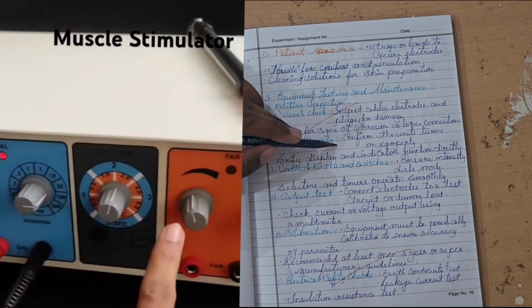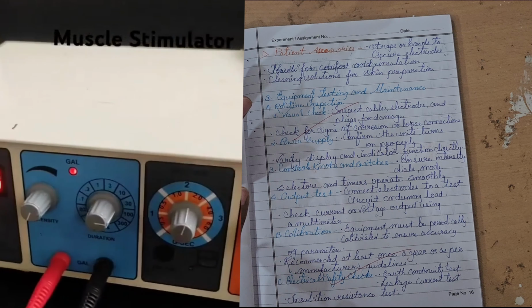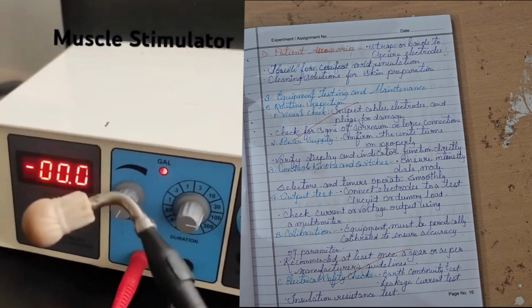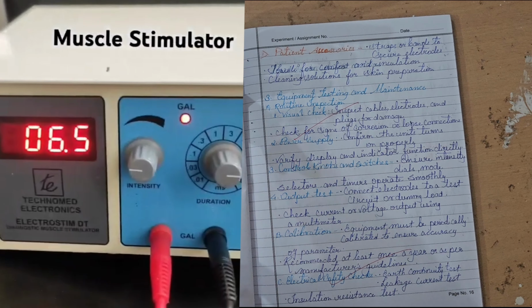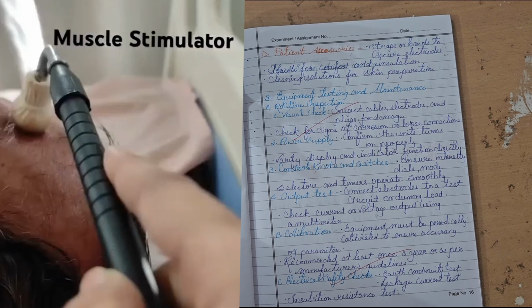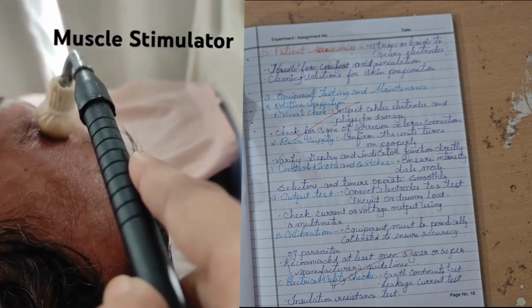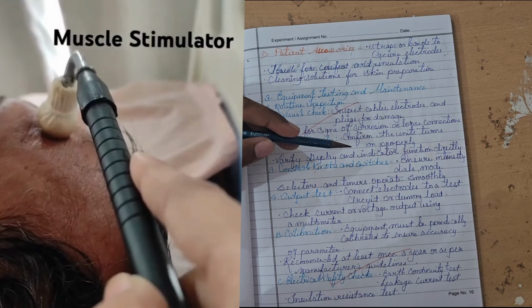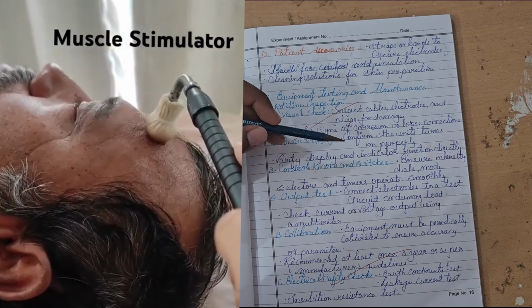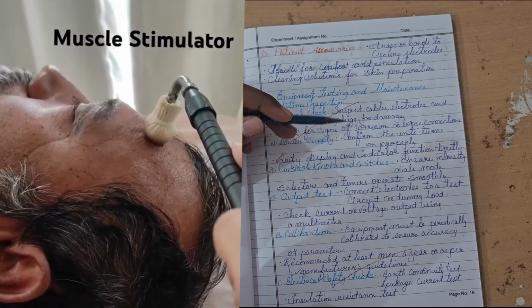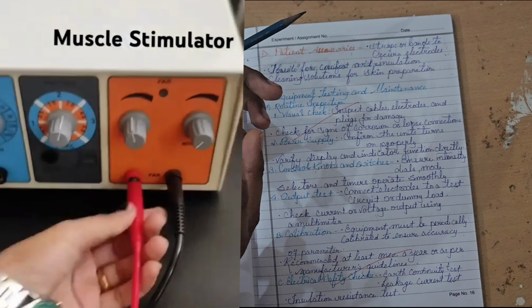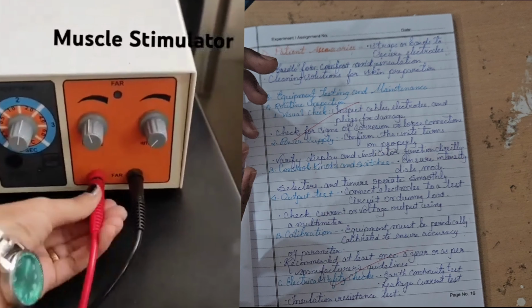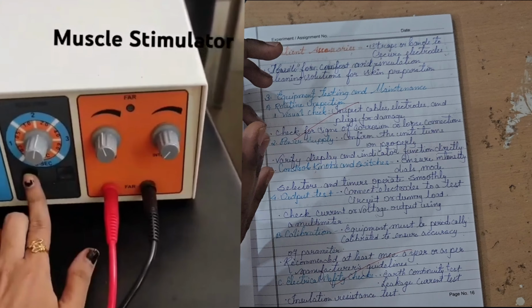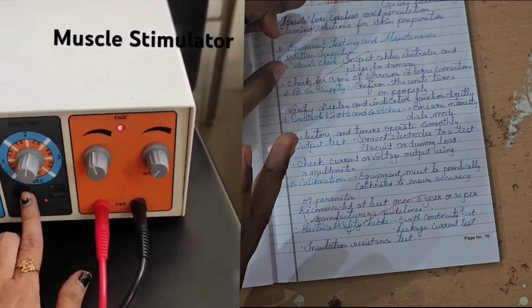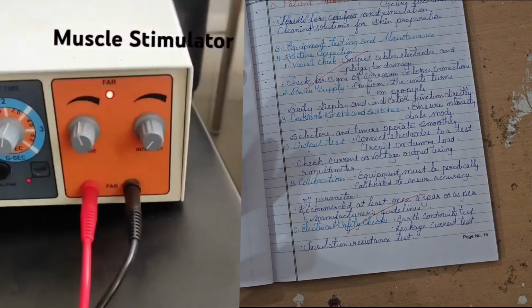Verify display and indicator function directly. So the power supply you can check by the indicator, applied on the skin directly. Control knobs and switches: you can check the switches and knobs. Ensure intensity dials, mode selectors, and timer operate smoothly. Before applying any kind of electrode gadget to the patient, you must ensure the time is appropriate for the patient or not. Check the connection to the skin, whether it is okay or not.